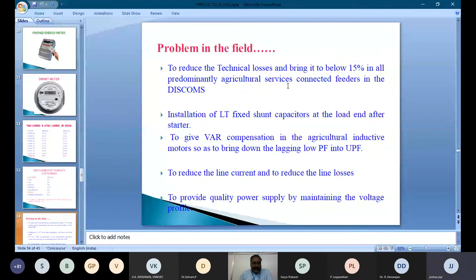So the agriculture sector is the unattended area. What do we have to do? We are proposing the installation of shunt capacitors at the load end after the starter, to give full compensation. All the induction motors run at a low PF, for example at 0.5 lagging PF or 0.45 lagging PF. But they need not pay a penalty for running the motor at a low PF in the agriculture sector.